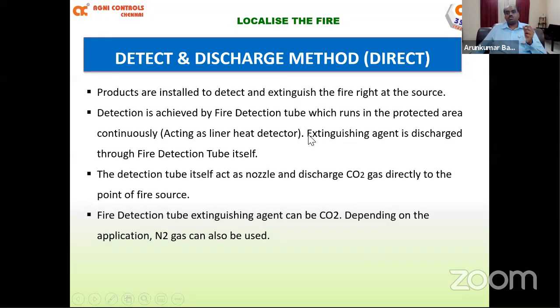Detection is achieved by the fire detection tube, which runs continuously in the protected area. The extinguishing agent is discharged through the fire detection tube itself - that is, the detection tube acts as a detector as well as a nozzle. It will discharge whatever content is in the extinguishing cylinder.